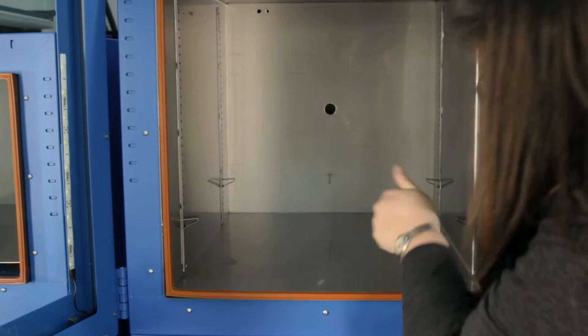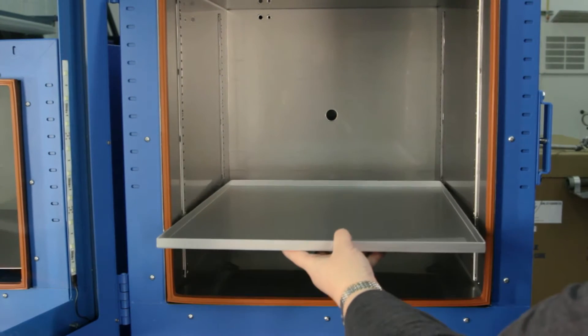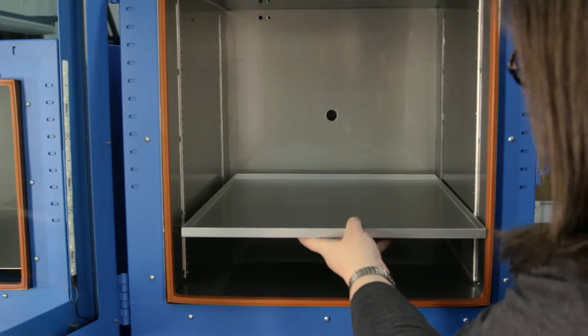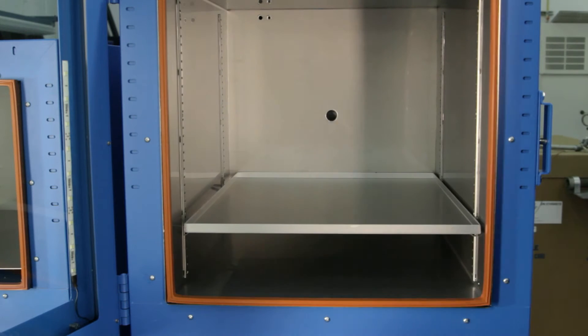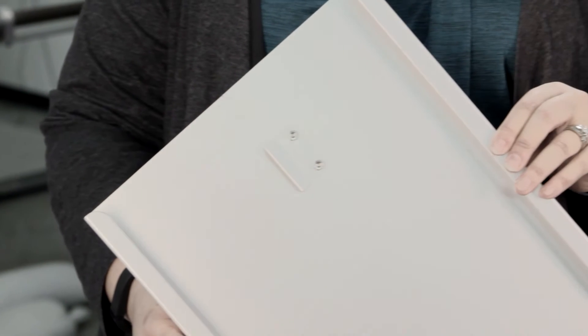In the case of the TVO5, you'll use the shelf clips to select the lowest possible placement for the shelf without putting any pressure on that probe. In the TVO2, you'll be using the clip on the bottom of the small shelf to clip onto the temperature probe.